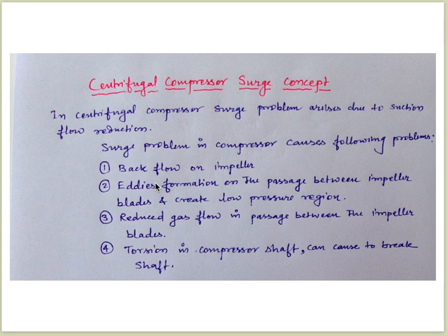In the centrifugal compressor, surge problems arise due to suction flow reduction. Normally when we talk about the centrifugal compressor, we define the suction conditions in the data sheet. The vendor also defines suction conditions at normal temperature and pressure. If the suction flow is reduced, it can cause the surge problem in a centrifugal or turbo compressor. Surge problems in a compressor cause the following: first, backflow on the impeller; second, eddies formation on the passage between impeller blades creating a low pressure region.